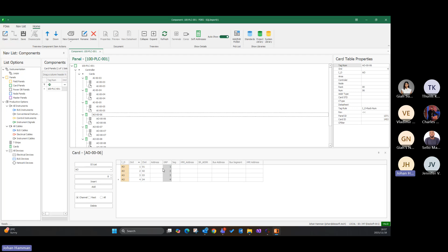So if I now click on my card panels, I can see there's my PLC, and inside here I can see all the different cards that have been created for me. So there's my analog input card, and I can quickly define my slot addresses, and Alt down will increment it for me. So I've got my slot addresses defined. There's my terminals for this analog input card. Then I've got my analog output. I can define my analog output slot addresses. And there's my analog output terminals.